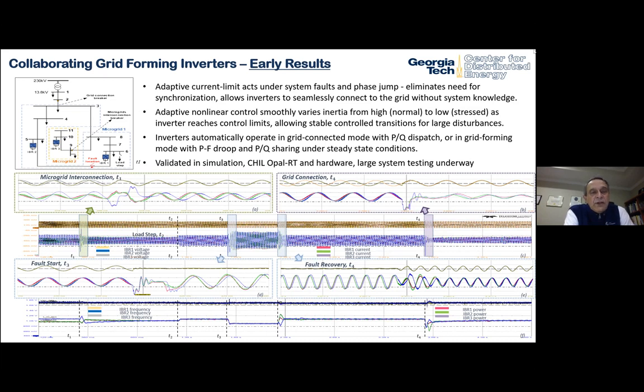We see an adaptive current limit that acts when there's a system fault or a phase jump. I think we're going to change how this is done, but this is a good implementation of functionality that has been very challenging to achieve—it eliminates the need for synchronization, so inverters can seamlessly connect to the grid without any system knowledge.